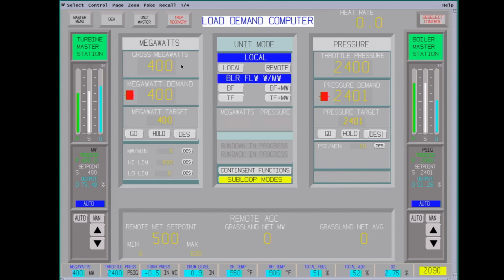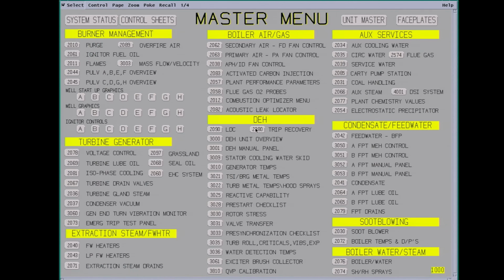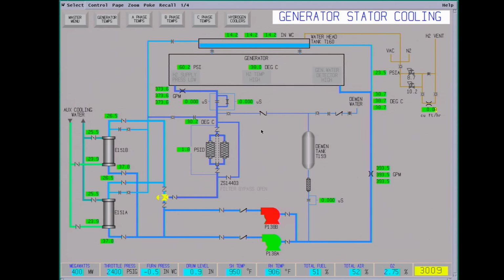Okay, today we're looking at a generator overview for a coal plant. The generator itself is capable of putting out about 625 megawatts. Right now running about 400 megawatts. Some of the quick overview screens. The reason we can get the higher output out of this unit, it has stator water cooling.